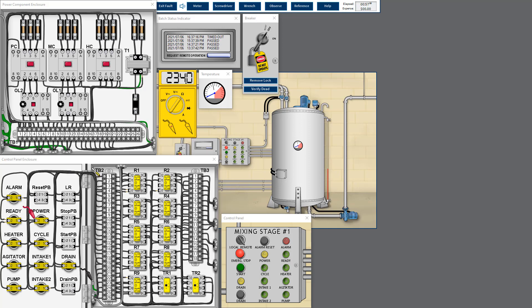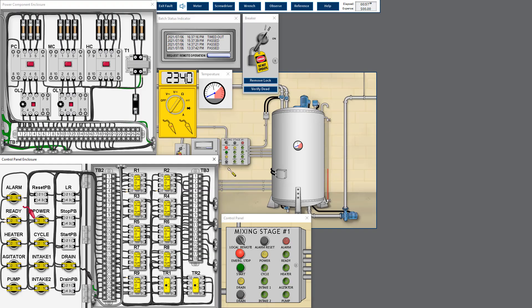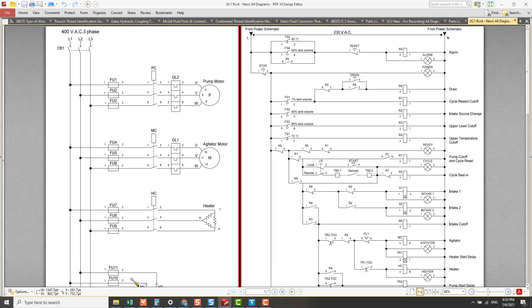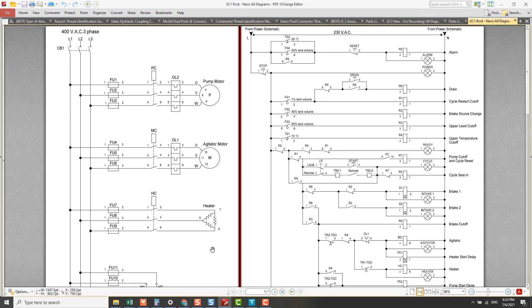I will not check the earth fault after the load because the resistance remained the same before the load and at the load, meaning after the load it will also be the same. So I normalize back the wiring connection and move on to other circuits.